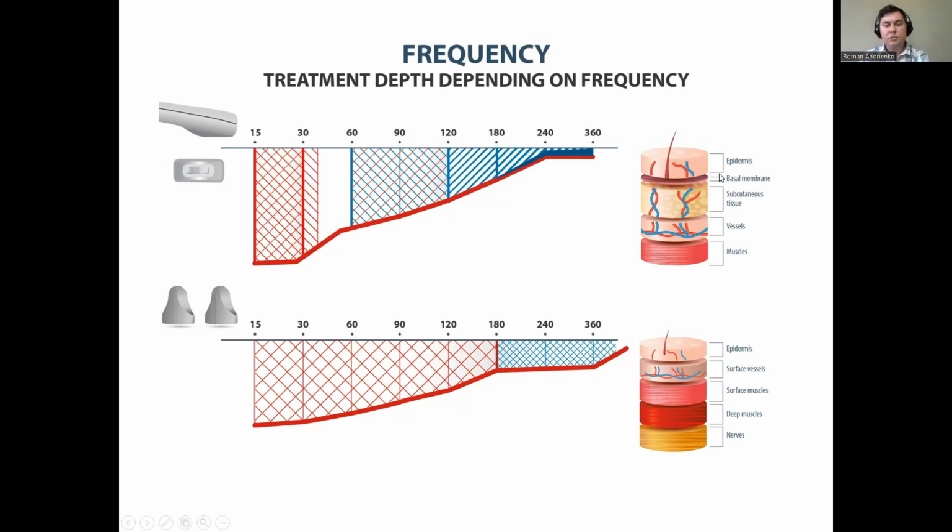we are able to only work with this amount of body structures, because it doesn't matter how low you put your frequency. If you're using the built-in electrode, the maximum depth that you can achieve is only about 2 centimeters, right? And it will look like a cone looking downwards into the patient's body like that, only maximum 2 centimeters deep.